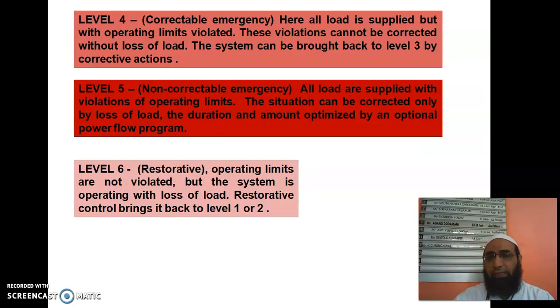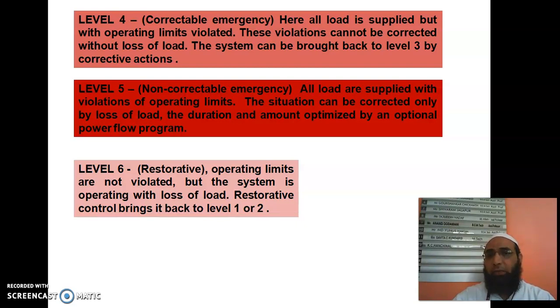Level 4 is also called correctable emergency. Here all load is supplied but with operating limits violated. These violations cannot be corrected without loss of load. The system can be brought back to level 3 by corrective actions.